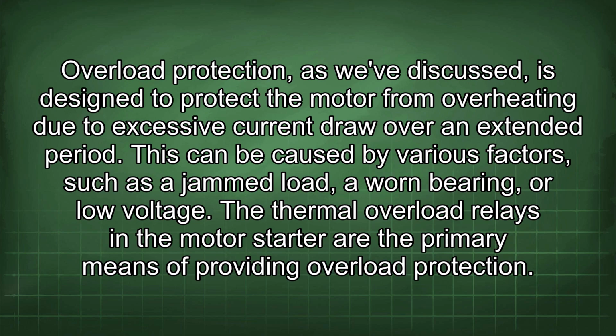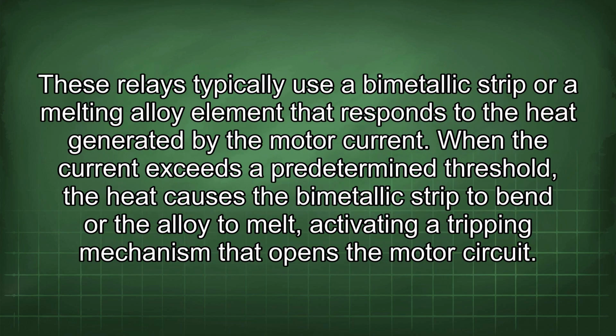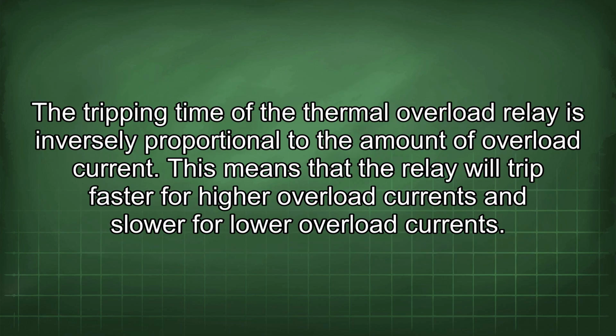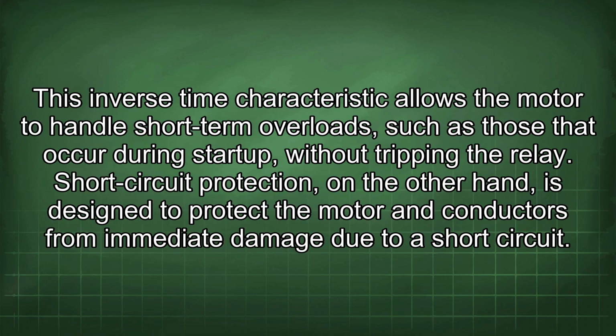The thermal overload relays in the motor starter are the primary means of providing overload protection. These relays typically use a bimetallic strip or a melting alloy element that responds to the heat generated by the motor current. When the current exceeds a predetermined threshold, the heat causes the bimetallic strip to bend or the alloy to melt, activating a tripping mechanism that opens the motor circuit. The tripping time of the thermal overload relay is inversely proportional to the amount of overload current. This means that the relay will trip faster for higher overload currents and slower for lower overload currents.